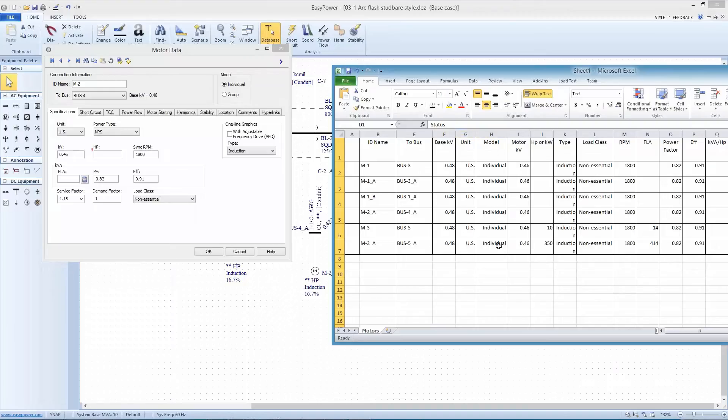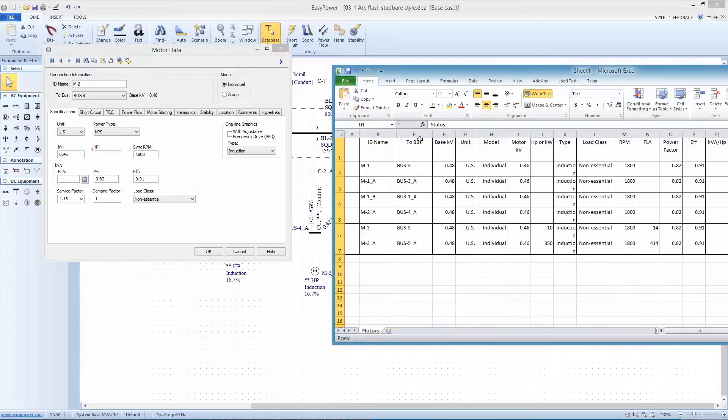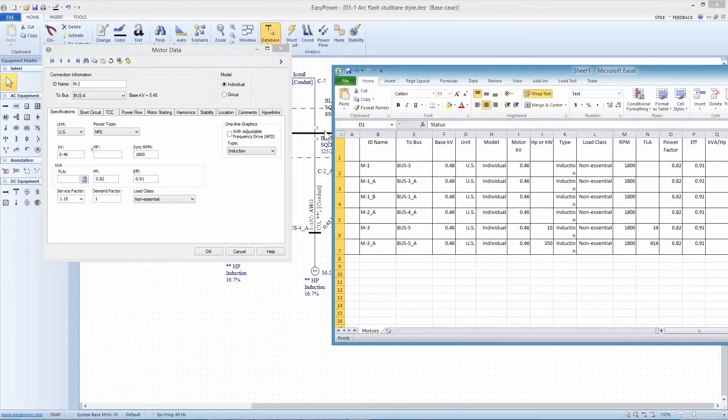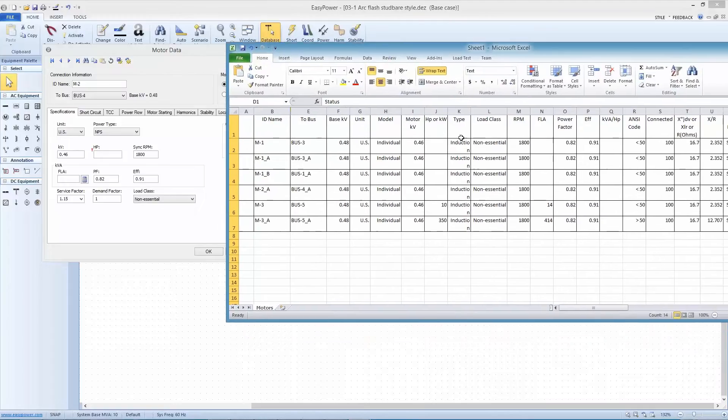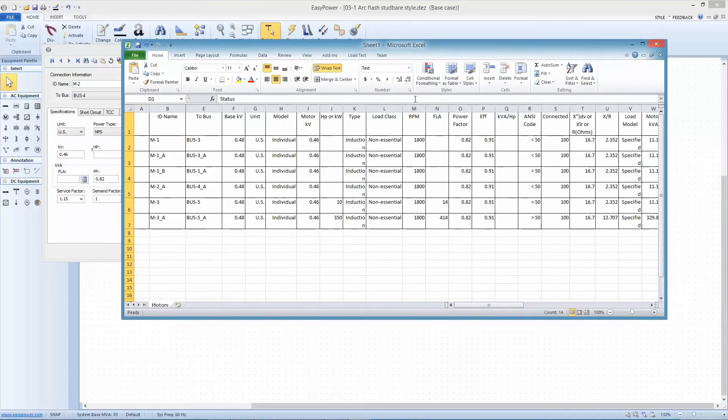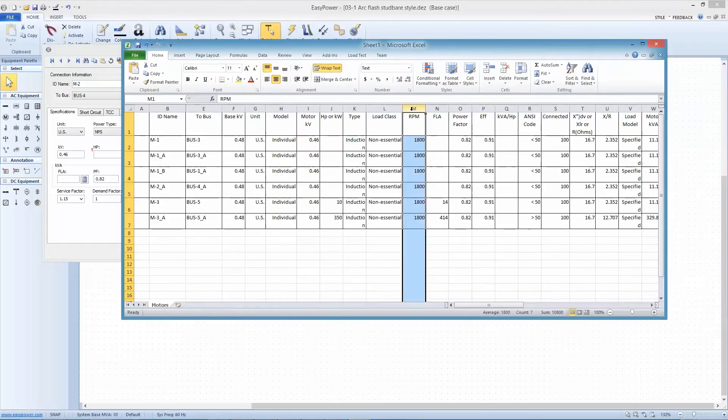Now the model, this says individual. As I'm collecting data, at least on the first time, I probably want to record everything individually. It turns out though we can group the motors. Let's say we have a bus with a lot of small motors. Rather than have to detail each one out, we may want to put one lump sum. Let's say we had 20 motors that were all half horsepower. We could set up a group that was 10 horsepower and be able to meet the needs of the study that way. It's something to play with once you actually start working with your system. Type of motor is important. Load class may or may not be important. RPM, we may have specialized motors where that's important. For my case, I believe everything's 1800 RPM, so I'm going to take this out.